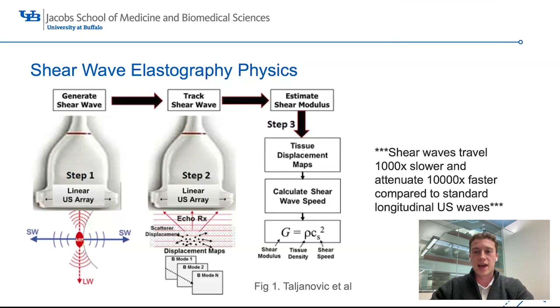It's a little bit confusing, but what's interesting is that the displacements that the shear wave creates on the soft tissue can actually be tracked down to the size of microns. It's very impressive, the shear-wave elastography equipment and how exact it can be. You get a number for the shear modulus, and you can understand a little bit more about the stiffness of tissue. It's worth mentioning also that these shear waves travel 1,000 times slower than a conventional ultrasound wave, but they attenuate a whole lot faster too, which makes tracking them both easy and difficult to catch and capture because of that fast attenuation.